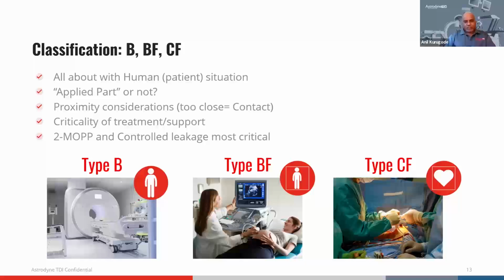Then there's body floating, where some part of the system, a diagnostic tool, is actually connected to the patient body. In other words, the patient is in electrical contact with what we consider the secondary side, the non-hazardous side. But the reason it is non-hazardous is it is by design, after recognizing it is going to be used this way with a patient electrically tied to the circuit. Nothing is accidental. So defining the product as BF automatically means I have to contain the leakage current going through the patient body as well as meet the two MOPP insulation. And CF, obviously, is the most rigorous one, where they're in very close proximity to the heart.